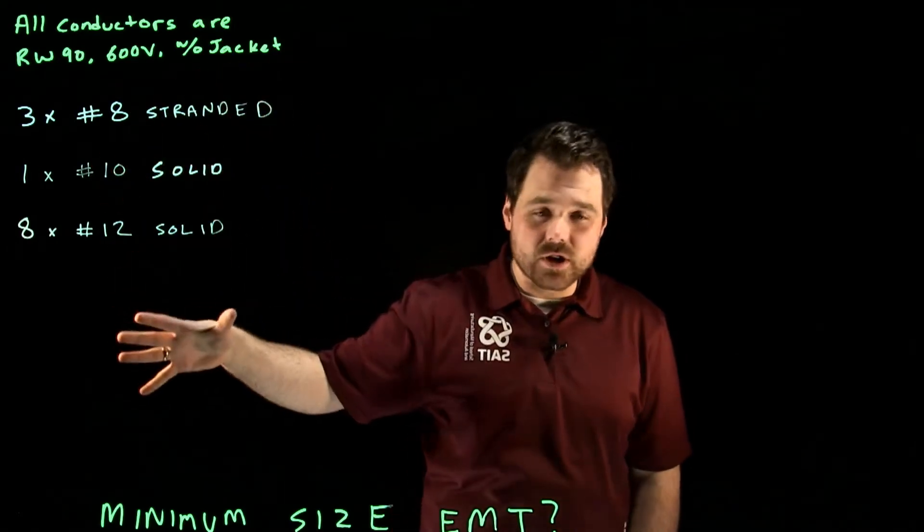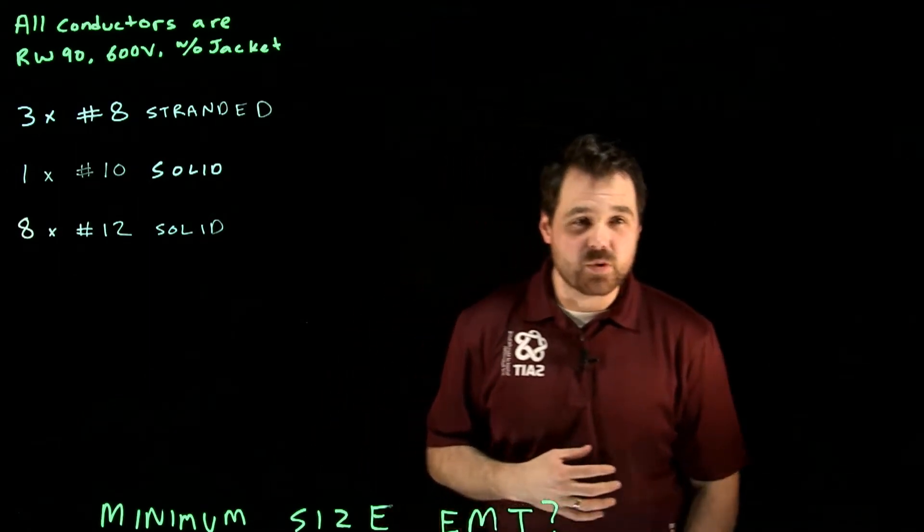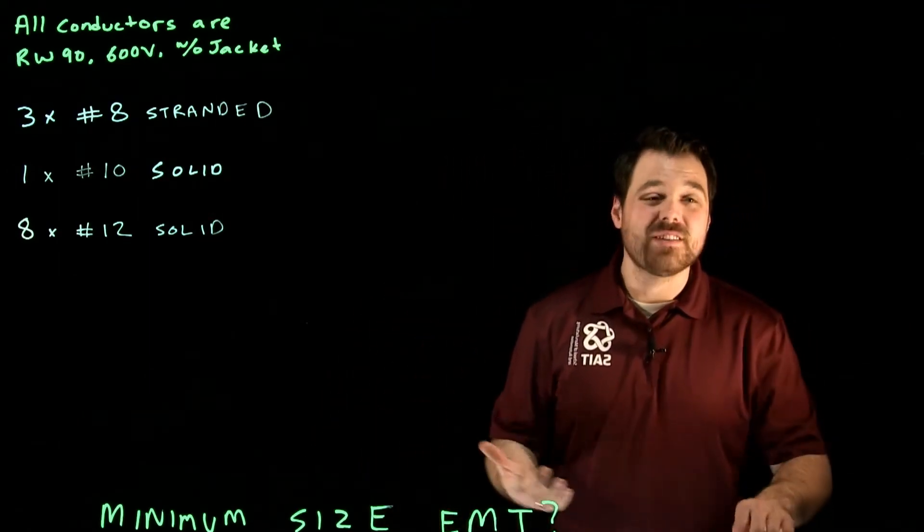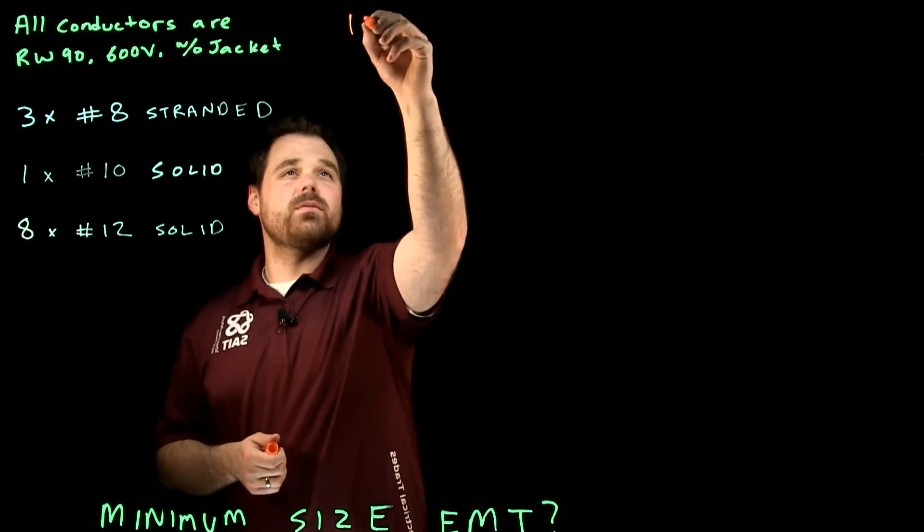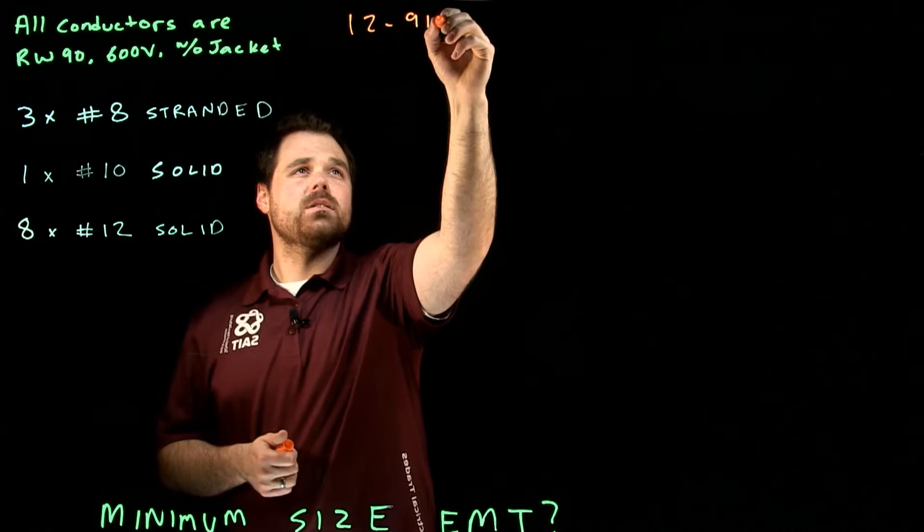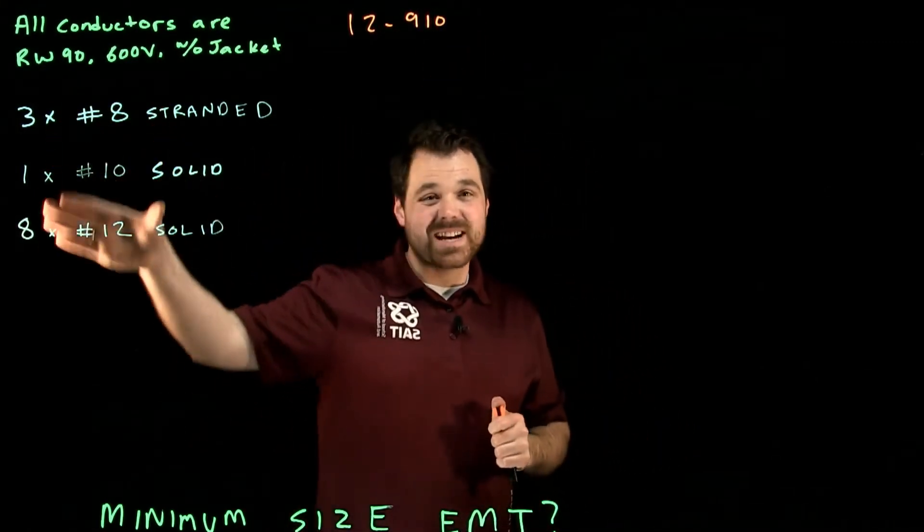We're pulling them into a conduit and we want to know what is the minimum size of EMT that I'm allowed as per 12-900 in the 2015 Canadian electrical code. So we're using 12-910 to size these conductors because there's multiple different sizes of conductors.